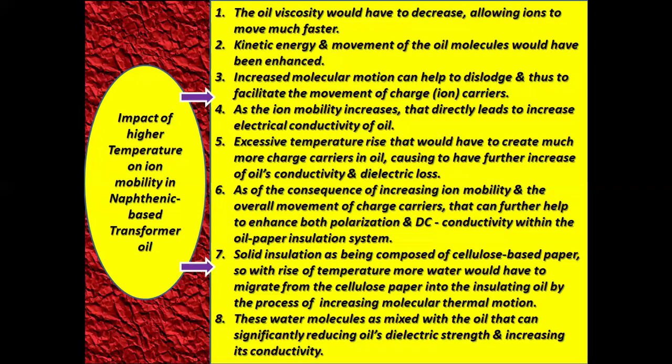As a consequence of increasing ion mobility and the overall movement of charge carriers, that can further enhance both polarization and DC conductivity within the paper insulation system.